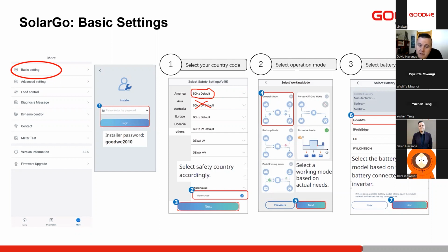Next is economic mode. Economic mode is used for time of use tariffs. Typically, we can also use it for a bit more dynamic charge and discharge. For instance, I use it in the morning to make sure my battery is at a certain percentage, so should the power fail in the morning when the family wants to make some coffee, there will always be battery capacity available. But I don't make it full in the morning because I want the sun to also do some charging. And then in the evening, the same thing as well. Lastly, for the ET and bigger devices, we also have the peak shaving mode, so we can select the work mode or peak shaving mode.